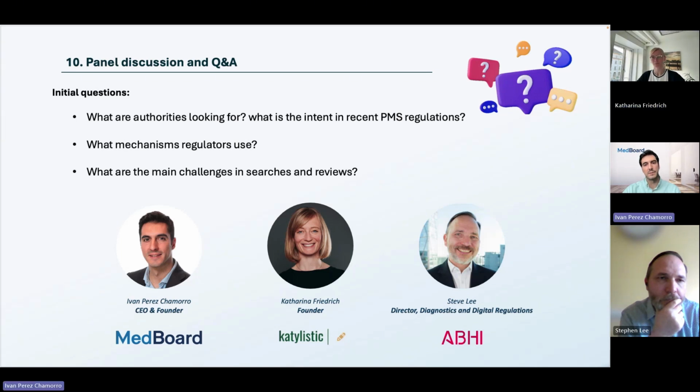And from your side, Steve, do you think that regulators should put more emphasis on manufacturers or professionals learning quicker? What are the expectations as well? Yeah, I think the pendulum has swung slightly the other way now. Instead of the regulator saying I have enough evidence to say your device is unsafe, there's a lot more emphasis on the manufacturer saying no, I have sufficient evidence to say that my device is safe and performs as intended.